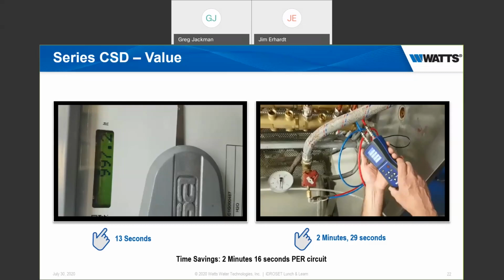Okay, next question. No systems are perfect out of the box after install. Sometimes there's air or dirt in the system. How does the valve deal with this? Good question. Our recommendation is that if this is a totally new system, once you're done with your standard flushing procedures, there should be no issues whatsoever. We do, however, advise that if you are retrofitting the iDROSET into an existing system that has a lot of ferrous components, and most of the old systems do, they have steel pipe, they might have cast iron boilers, cast iron circulators and other components. We still recommend flushing the system, but the best way to deal with that is to install one of our Y strainers upstream of the iDROSET to protect it from those older systems that probably have quite a bit of debris floating around in them, no matter how much you try to flush them. One of our Y strainers, like the 777, will do a good job of protecting the iDROSET from that.